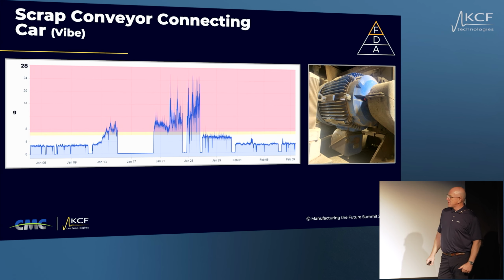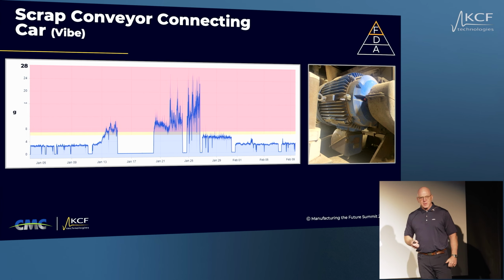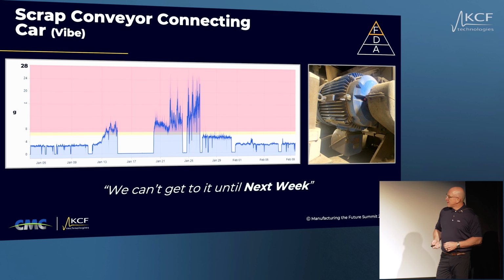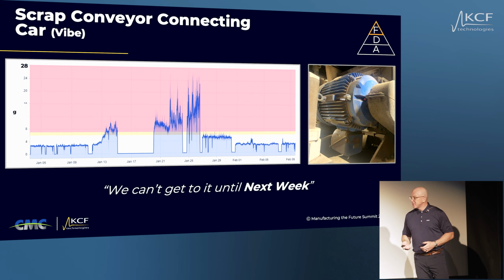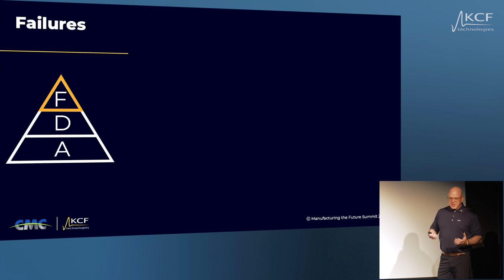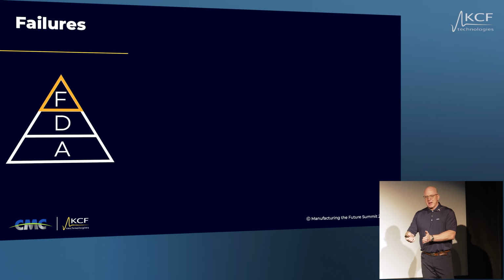By nature, this is on a shaker table, so the baseline vibration is set very high. Some of the shaking is filtered out, but we did have an issue with a motor, and we planned to change the motor, but we couldn't get to it until the following down day. So we had the motor staged, down days Wednesday every week. And as it says, we can't get to it until next week, but unfortunately, the motor failed the day before. So that was a failure. That was 6 to 8 hours downtime, but we'd seen the abnormality, we knew there was a defect, we planned to change it before the failure, but we were a day short.